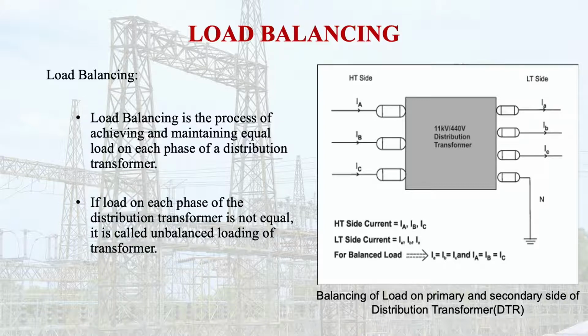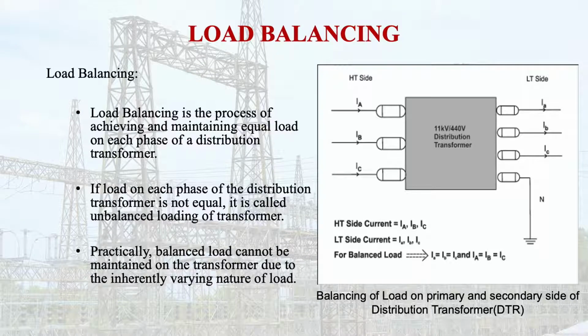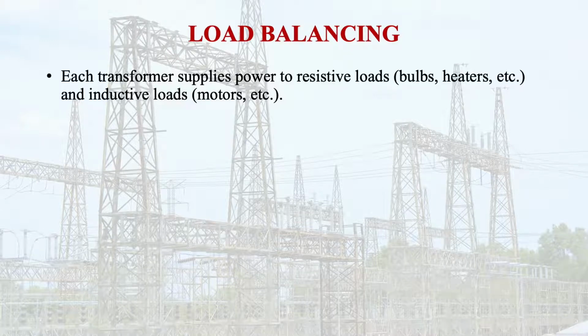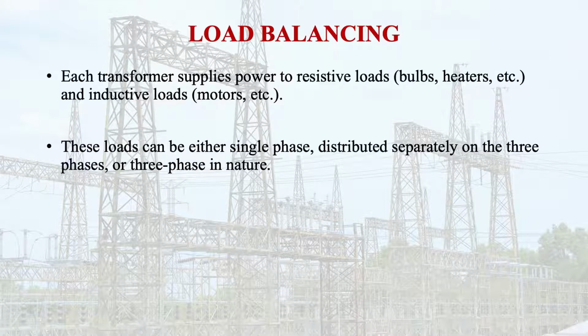The balancing is required. If the load on each phase of the distribution transformer is not equal, it is called unbalanced loading of the transformer. Practically speaking, balanced load cannot be maintained on the transformer due to the inherently varying nature of the load. You know very well that the secondary side is connected to the consumers, and it is very difficult to maintain equal load on each phase. Each transformer supplies power to resistive loads, which can be bulbs, heaters, and inductive loads, which can be motors or big machines. So these loads can be either single phase, distributed separately on three phases, or three phase in nature.